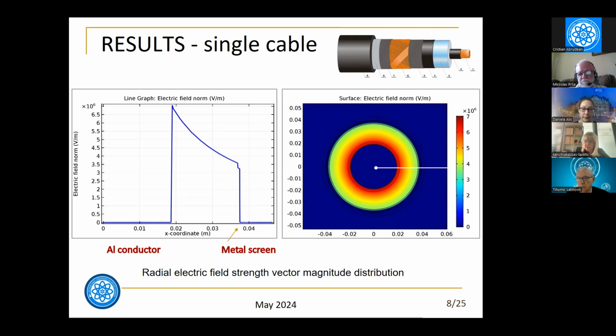Inside the insulator layer, the magnitude of the electric field strength vector decreases as 1/r up to the cable metal shield. Inside all external cable layers, the magnitude of the electric field strength vector is again equal to 0. This fact means that the metal screen is really a perfect protection against extremely low frequency electric field. So we will take into consideration after that only the calculation of the magnetic field distribution.